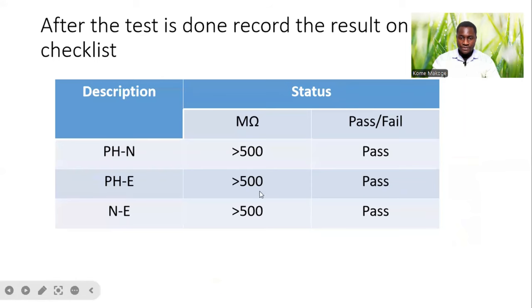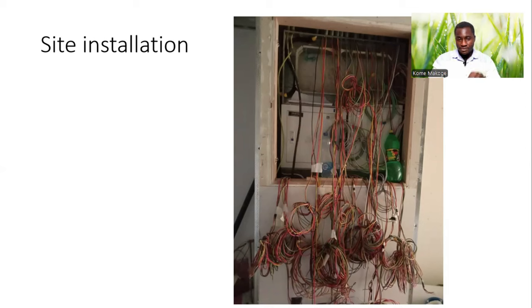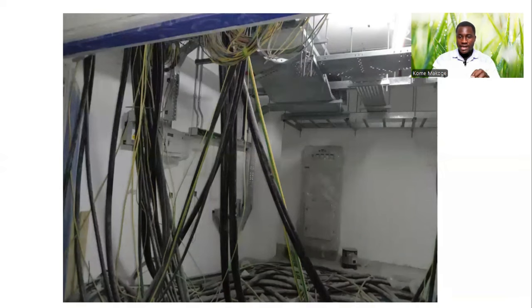Once we are done with the test, we record our different readings and note the status — either pass or fail. In this case, we had all pass. This is a site condition where we have all our different wires and cables pulled for both incoming and outgoing, which is the prerequisite. We have to make sure that we pull them with identification labels prior to performing our insulation resistance tests.